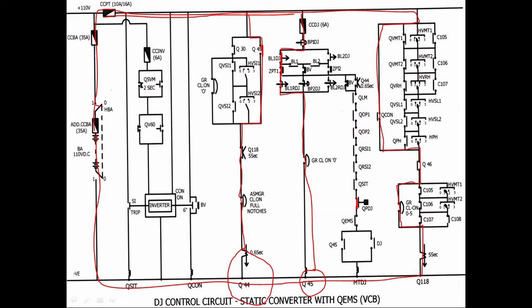Once Q44 is energized, on Q45 branch below ZPT interlock, since Q44 is energized, its normally open interlock is closed, and since all safety relays are in de-energized condition and QPDJ is already closed and BPMS is not in pressure condition, that is QEMS is in de-energized condition, since Q45 is energized, its normally open interlock is closed and MTDJ branch gets supply. Now once MTDJ branch is energized, DJ is closed.